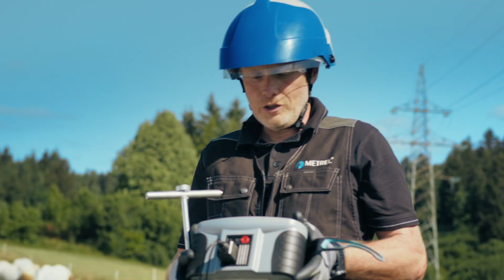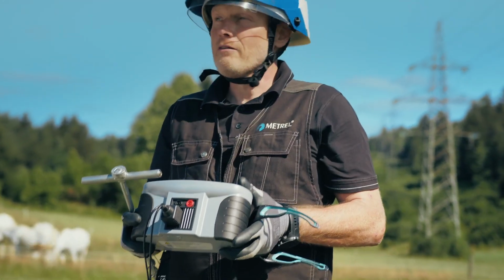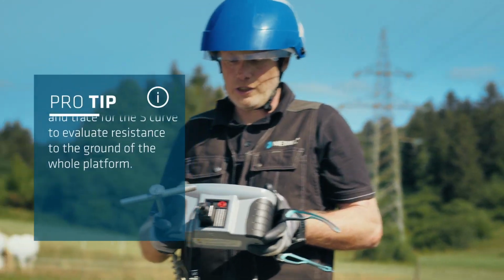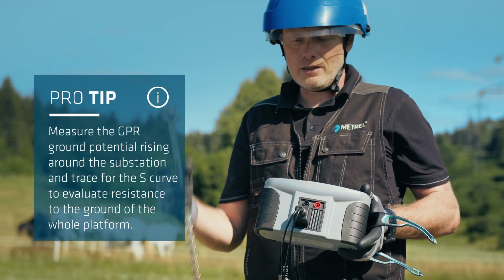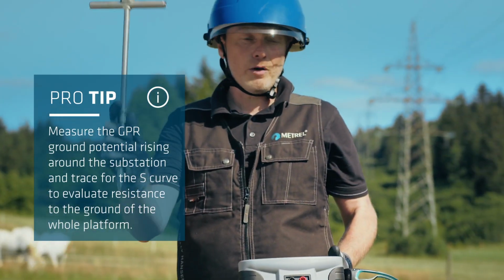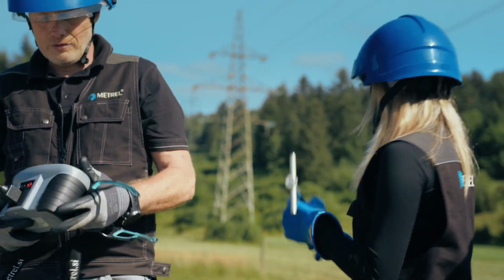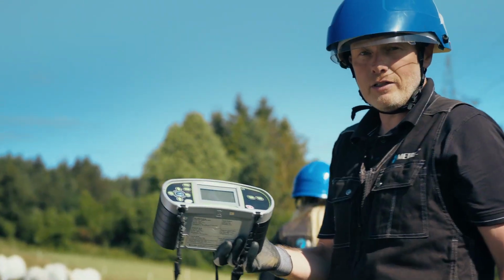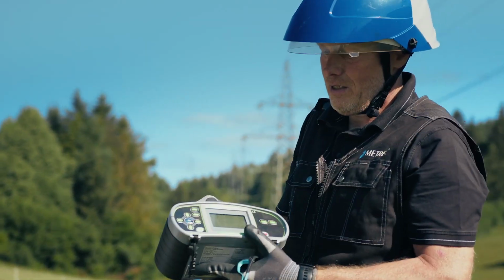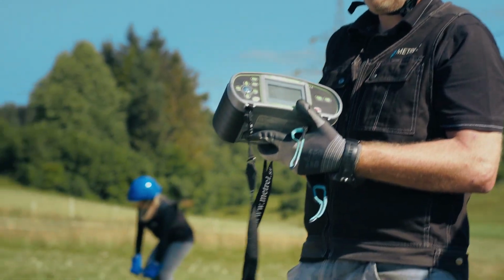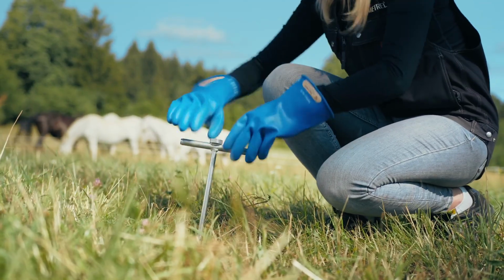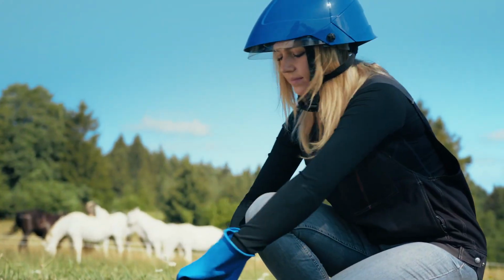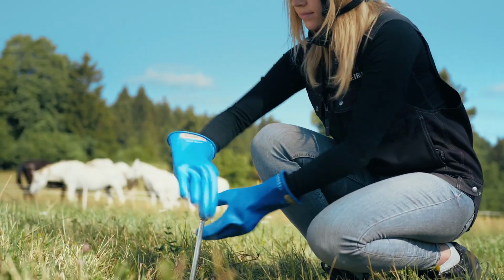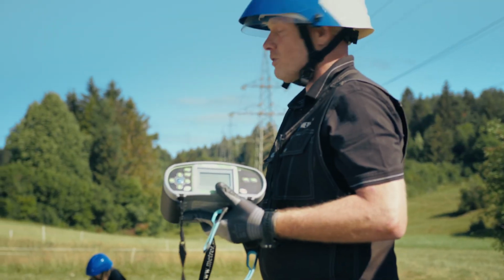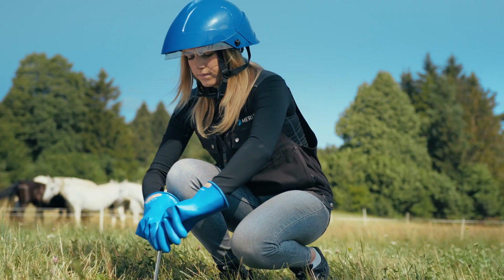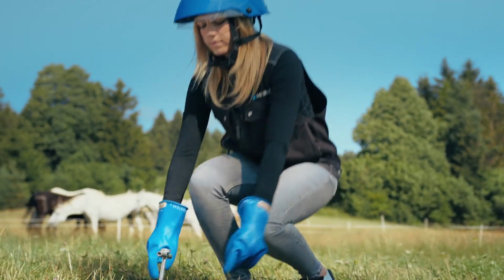Well, we have the generator running. We will measure the voltage potential between the substation and the surrounding. For that purpose we will use this probe and this voltmeter. The voltmeter will serve us for measuring the difference between the substation and the potential on the field. We need to measure it several times for fall of potential, to establish where the flat part of the S-curve of this voltage funnel is.